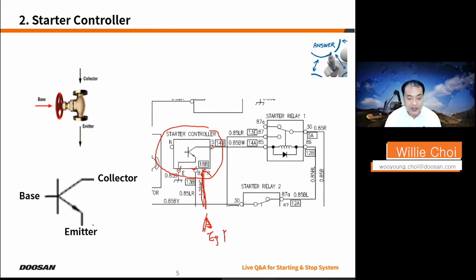That relates to engine RPM. If engine RPM is more than 500, the ground should be disconnected—no more ground. At that time this line is not connected to ground, so the position should be here, and that's why the starting signal does not go to the starter motor.